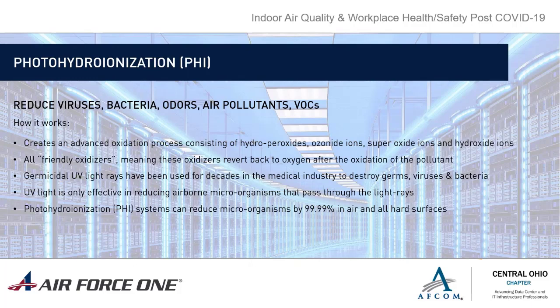There's a lot of misinformation out there where people actually think that the UV lights installed in your unit are disinfecting the air, which really is a misnomer. Because of the velocity the air moves and the fact that even at the microscopic level they can shade each other, to install enough UV in a piece of equipment to actually disinfect the airstream at a rate of 99% or above would take an extreme amount of power. The light intensity would be so large it would start to degrade anything that's not metal, and even probably cause issues with metal down the road. Any plastics or caulk sealers in that unit would degrade, and it would actually make your equipment fail.